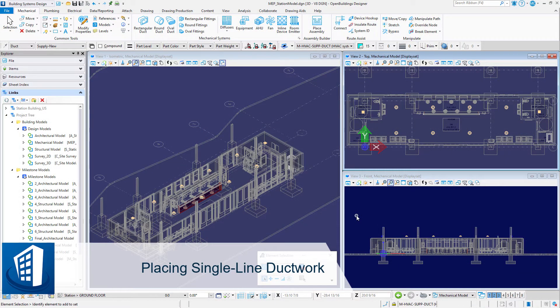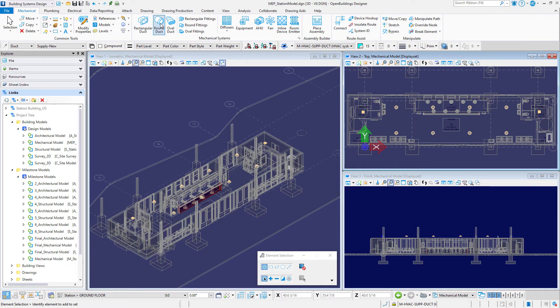Welcome to this session on modeling single-line ductwork. Routing in the mechanical discipline is a fully dynamic process in which fittings such as transitions, elbows, and branches are automatically placed without exiting the place duct pipe tools. The preferences for these fittings — for instance a radius elbow versus a mitered elbow — are determined by the auto-fitting preferences. To shorten the time spent on preliminary routing of a system, there is an option to initially model ductwork in a single-line mode.